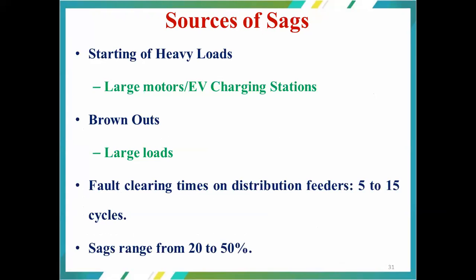So sources of sags are the starting of heavy loads by industries, large motors, or EV charging stations. Suppose a particular charging station is going to have 10 or 20 ports, and all 20 ports are operated simultaneously, which is going to have an impact on the nearby transformer or on the transformer located at the particular facility. And brownouts, again, due to large loads, a few megawatts getting immediately disconnected or immediately connected to the load, then this kind of brownout is going to occur.